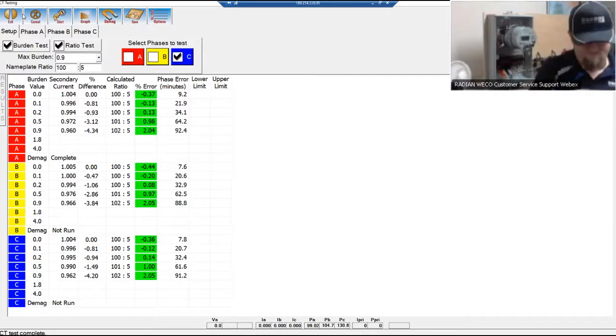And then as well, we have voltage cabling and a duckbill, one singular duckbill. So let me bring up the voltage cabling here. It's several feet long, so I've got it all across the floor. But it's got voltage cabling running from the output of here to an A-phase and neutral alligator clip. And then your duckbill end is one singular cable, one duckbill, going into the burden ratio test.